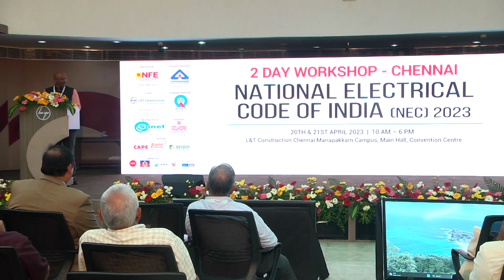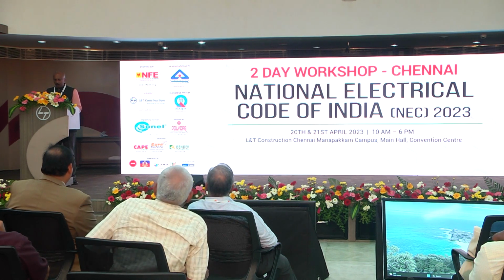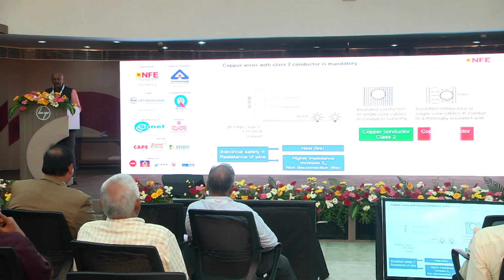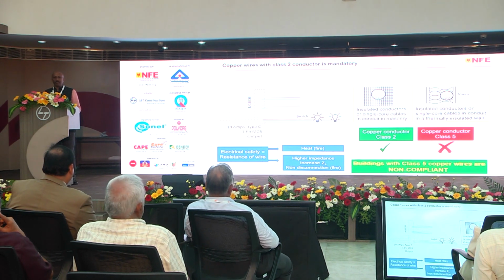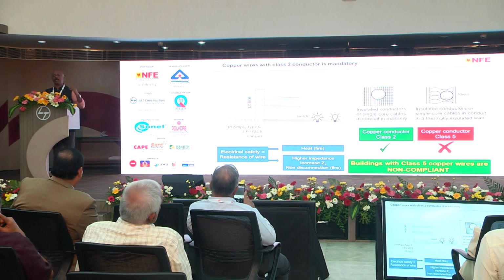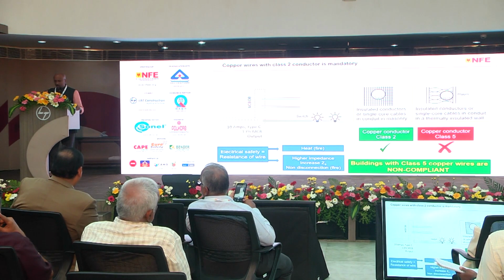the subject is compliance and non-compliance. It would be very nice to discuss. I would like to show you what new regulations and standards are going to come. Now, you know very well, we had a nice discussion in the morning. Class 5 copper wire is non-compliance. You can very soon find it out, probably once the electrical inspectorate engineers are aware of it, or the electrical safety auditors are aware of it, or the insurance companies are aware of it, then they will start insisting on class 2 copper wire.